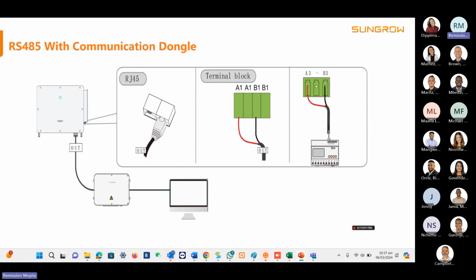And then we have the RS485 communication with the dongle. So basically, the setup for the dongle and the inverter is the dongle directly goes to COM3, and then the inverter and meter can go directly to the terminal port. So you can use A1, B1 if it's just one inverter and one meter, but if it's one meter and multiple inverters, the inverters will go directly to the A1, B1, and then the A3, B3, or A2, B3 in the old CX versions, is where you're going to connect the meter.